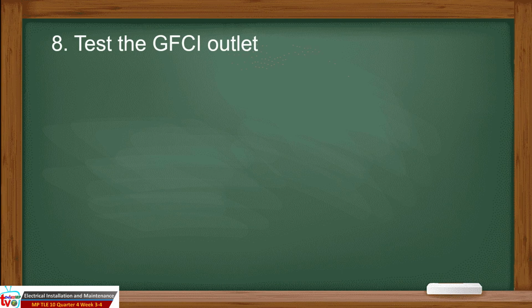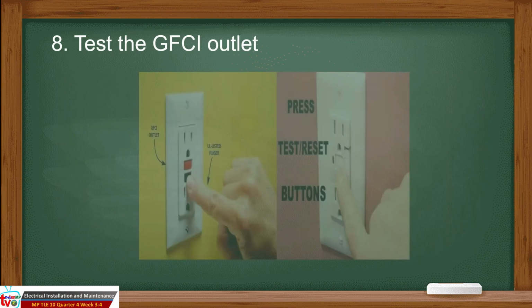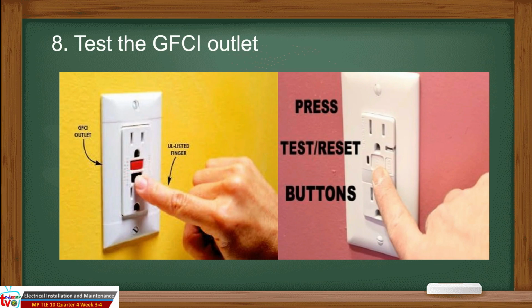Test the GFCI outlet. Number 1, press the test button, which should turn off the circuit. Number 2, make sure the power is off by plugging in a lamp, radio, or something similar. Next, press the reset button, which should turn the circuit back on. And last, check the power by plugging your device back in.